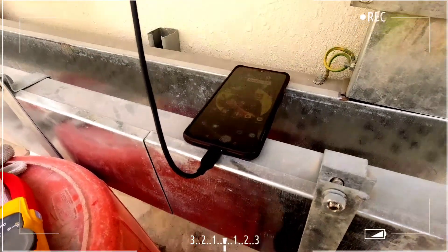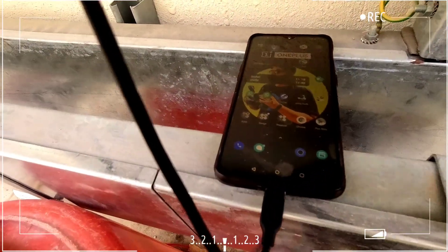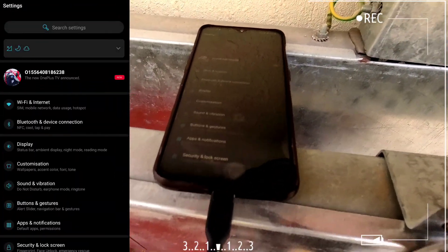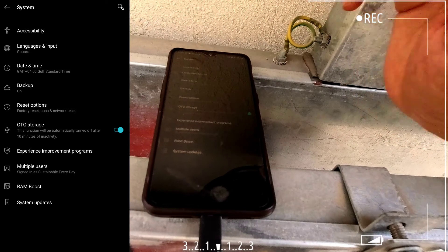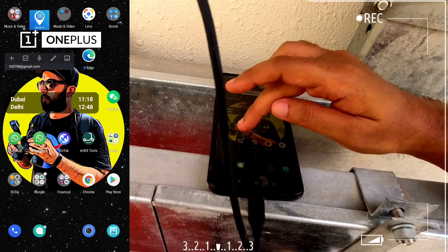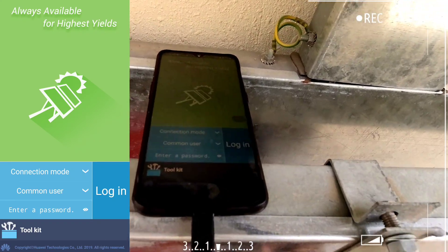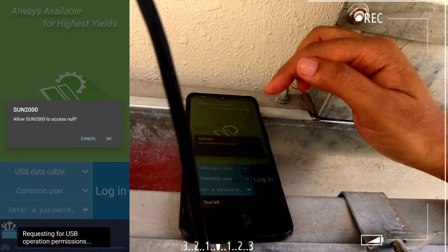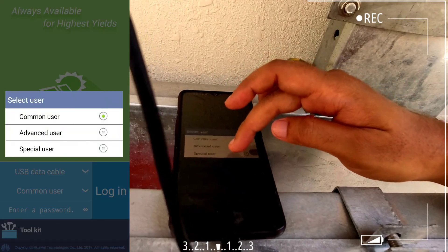Now you can see my phone is connected using the USB cable. Once connected, for Android 10 users especially, go to settings, then system, and check whether OTG is activated or not. Once OTG is activated, go back and open the SUN2000 app. In the app, under connection mode, select USB data cable. Then under common user, select special user to give the inverter access.